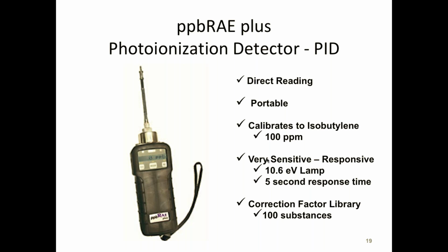Okay, and this is this particular gas. This cylinder has exactly 100 ppm by volume of isobutylene in pure air. Right, that's what we have here. So you use this device to calibrate this. You turn it on. Let me latch it. This regulator says that there's 0.3 liters per minute of isobutylene at this level in air escaping here right now.